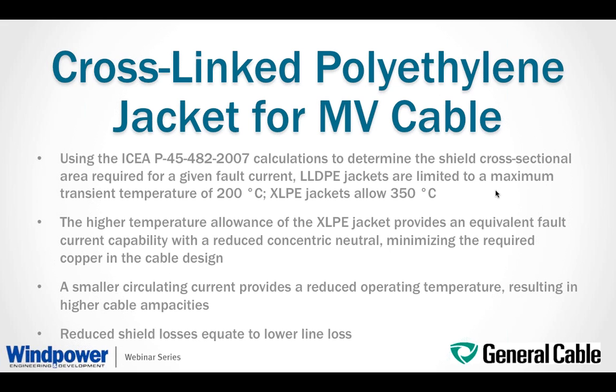So the enhanced properties and the better heat deformation of the XLPE jacket, in the end, what does it provide? It's again, when Brendan was talking about minimizing losses and optimizing your design and your neutral size to minimize the losses, with an XLPE jacket you can go even further, even further optimize the size of your neutral, and achieve even larger savings on losses.